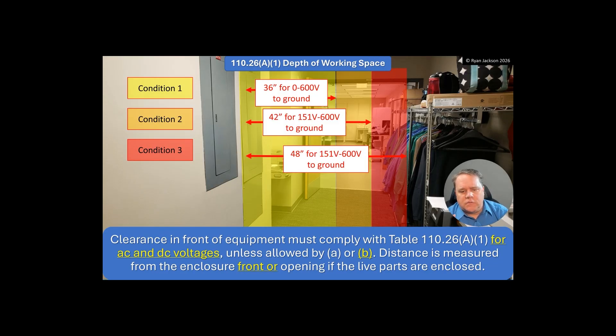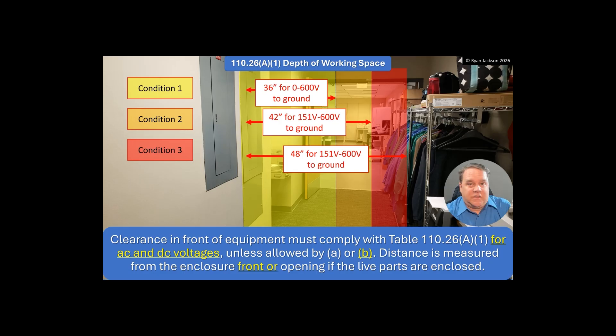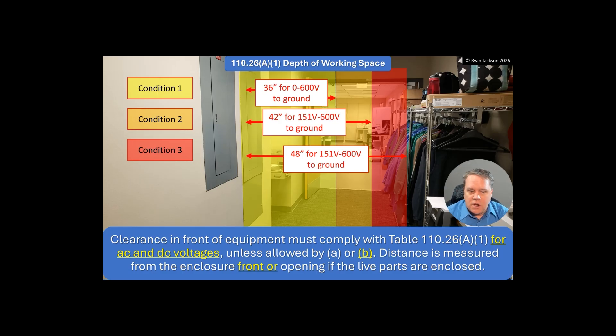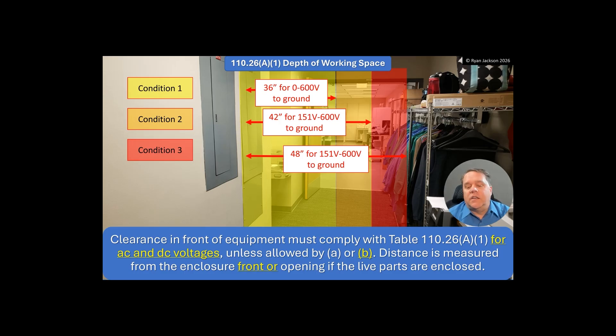AC and DC were both added explicitly. You could argue that because it didn't previously specify AC or DC it applied to both regardless, but now it specifically says AC and DC. Clearance in front of equipment must comply with Table 110.26(a)(1) for AC and DC voltages, unless allowed by A or B. The numbers don't change.